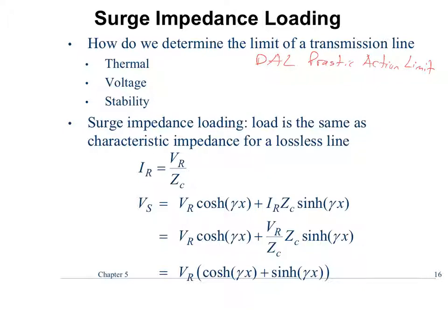That's a thermal limit. I'm just moving too much current through the line. And remember, it's only I squared R, right? Doesn't matter if you're moving real power or reactive power. The magnitude of the current is determined by both of those, so it's always I squared R. The next one is voltage limit, which basically we have some resistance and some inductance. I did that backwards.